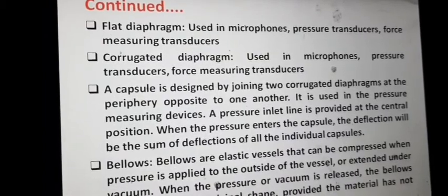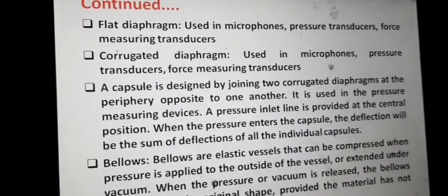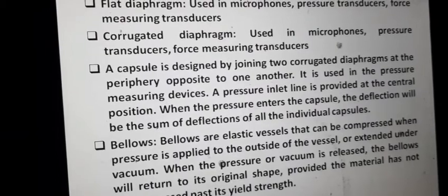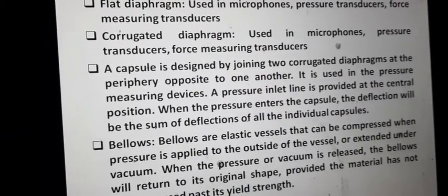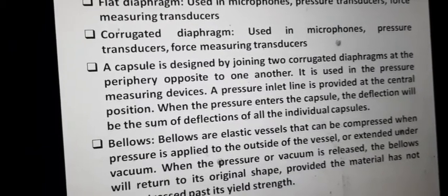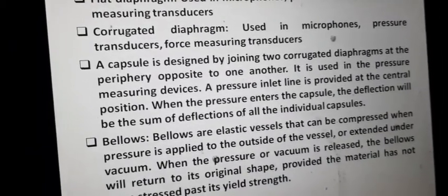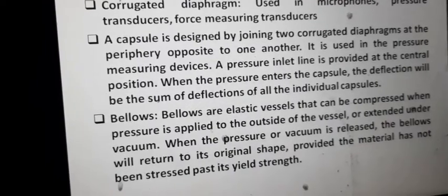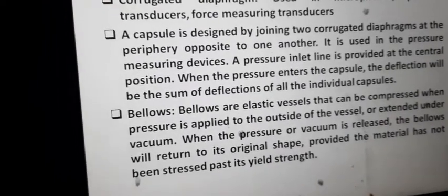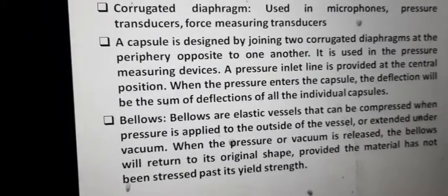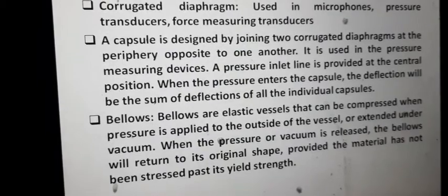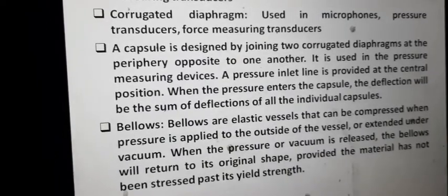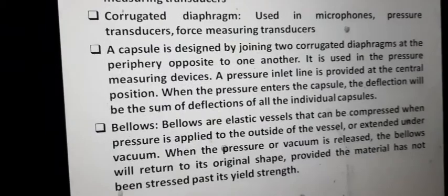Flat diaphragms are used in microphones, pressure transducers, and force measuring transducers. Corrugated diaphragms are used in the same applications. Capsules, which are two corrugated diaphragms joined opposite to one another, are used in pressure measuring devices — the pressure inlet is provided at the middle position so that when pressure enters the capsule it deflects, and from the displacement you can get the proportionate pressure reading. Bellows are elastic vessels that compress when pressure is applied at the outside or extend under vacuum, and they also act as actuating mechanisms by producing movement in response to force or pressure.